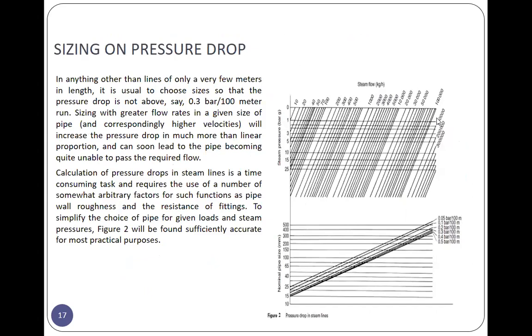So sizing on pressure drop naman tayo. Kasi kailangan ma-check mo yung pressure drop. And for anything other than lines of only a very few meters in length, it is usual to choose sizes so that the pressure drop is not above, say, 0.3 bar per 100 meter run. So, yun tayo para dito calculation.